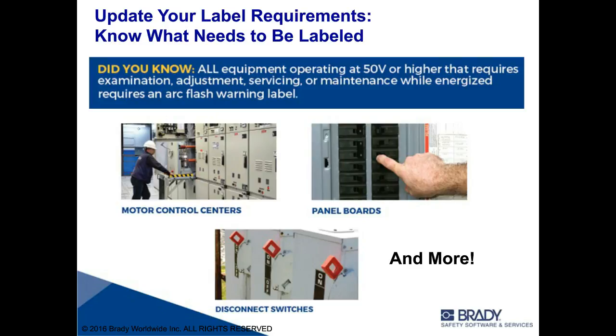But what's important to note is that both of those codes do focus on a 50-volt number, and OSHA talks about this 50-volt number as well. Anything over 50 volts that has the likelihood to be worked on while energized, and they talk about troubleshooting, maintenance, a lot of different things. So pretty much anything you're going to approach and be exposed to while energized over 50 volts should have a label. So a lot of times, disconnect switches.